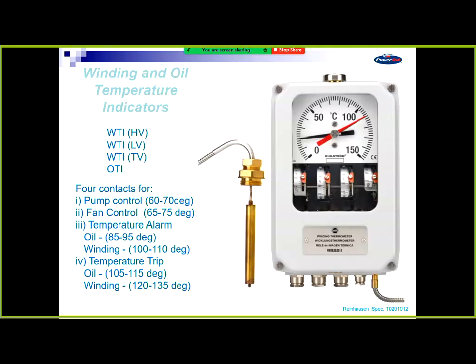So a long time ago we used to trip both the HV and LV, we didn't distinguish, then we started to think about it and said, this isn't a fault on the transformer where we need to de-energise the transformer, we need to deload the transformer. For us, when we energise a transformer, it's always from the high voltage breaker to the low voltage breaker, so we trip the low voltage breaker in that case.